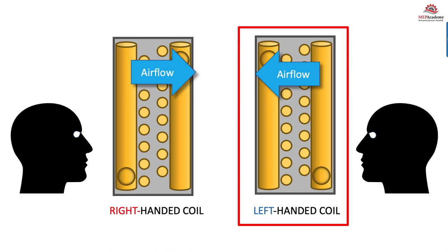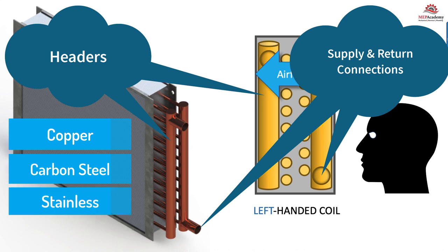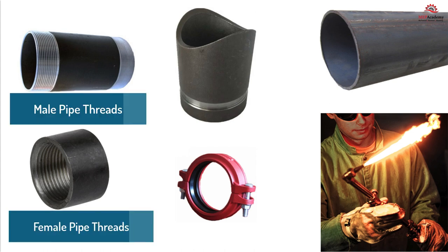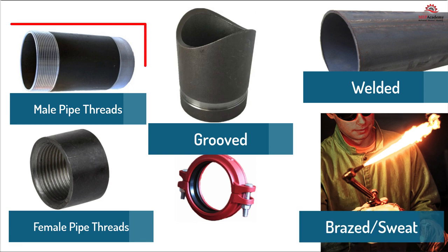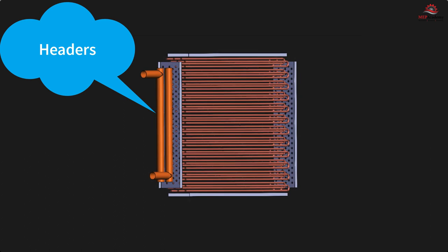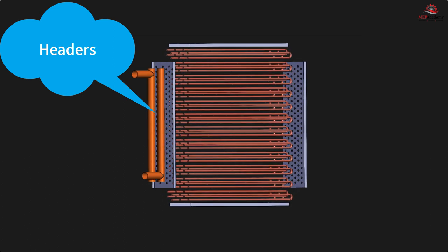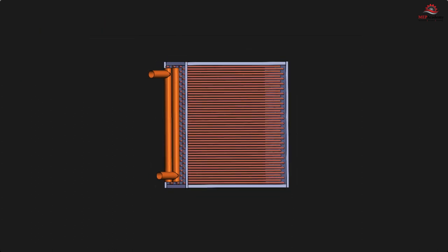Headers are provided for the supply and return connections to the coil, and can be provided in materials such as copper, carbon steel, stainless steel, and red brass. Piping connections can be provided in male or female threads, grooved, welded, or brazed sweat. Male threaded connections are common up to 2.5 inches. The header serves several purposes: it provides a method to connect all the individual tubes in the coil to one larger pipe, which can then connect the system piping to one or more inlet and outlet connections. The header allows the water to be distributed to the smaller connecting tubes.